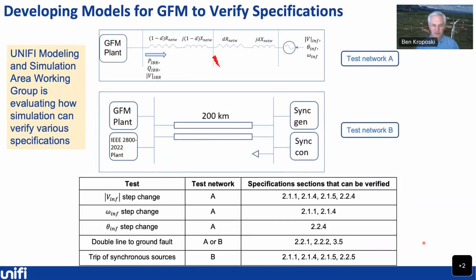So how are we taking all these requirements and doing some things inside our UNIFI Consortium to address these and validate that they're actually working? First off, we want to make sure that we're developing models for the grid forming technologies. So we have a working group that's working on modeling and simulation, building grid forming inverter plant models, and then wanting to figure out ways, with just the plant modeling capability, to look at evaluations of things like voltage step or frequency step and which specifications they can verify inside of that system.